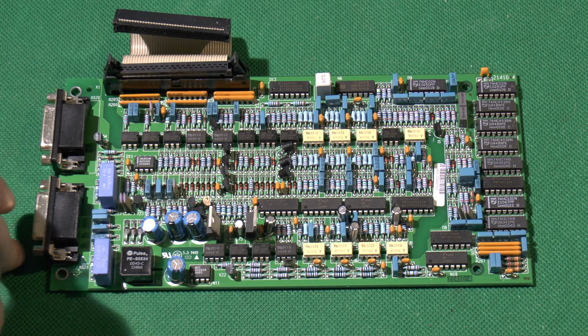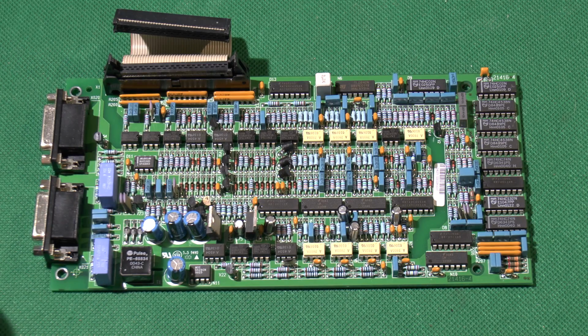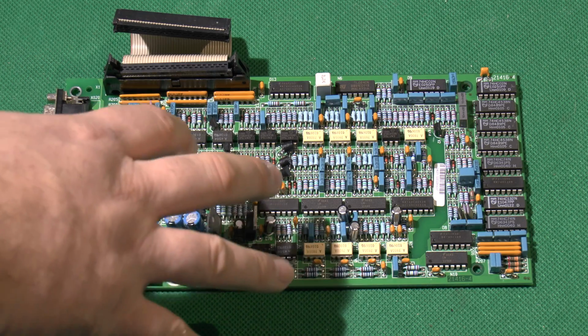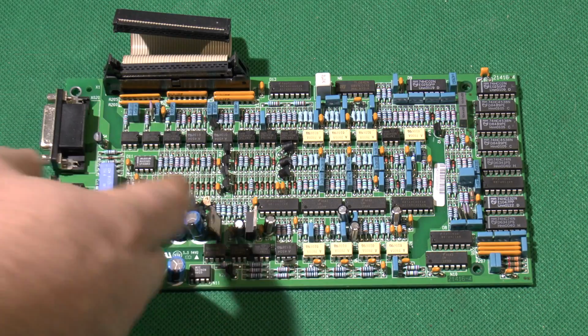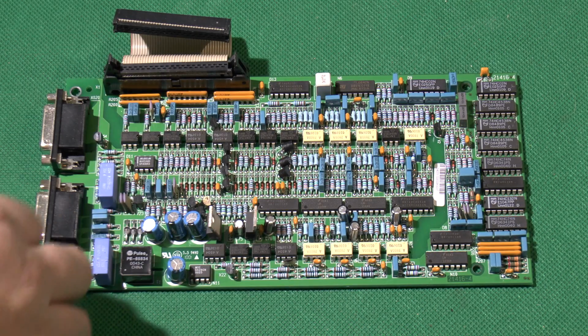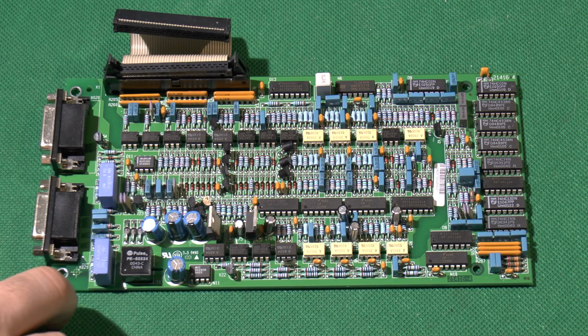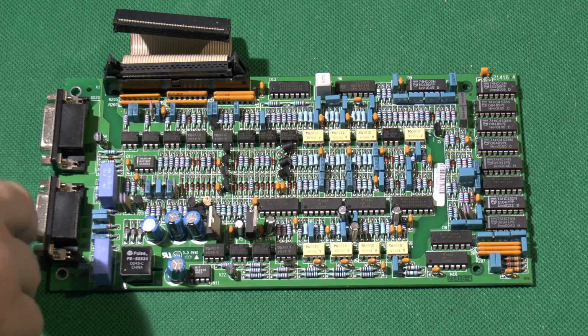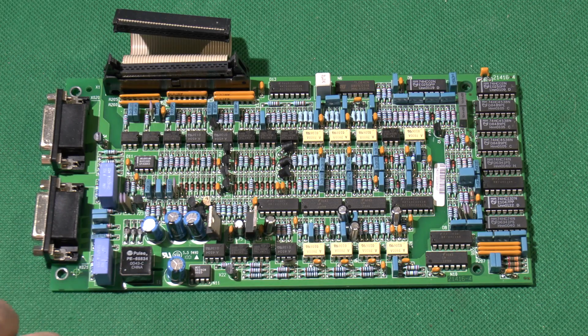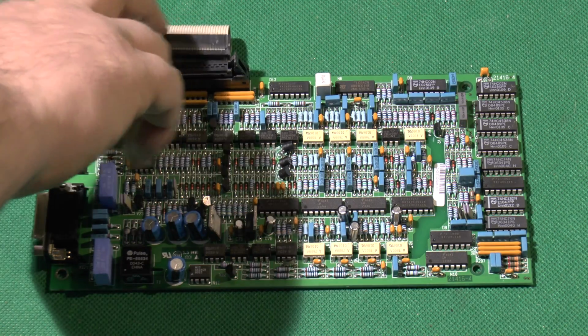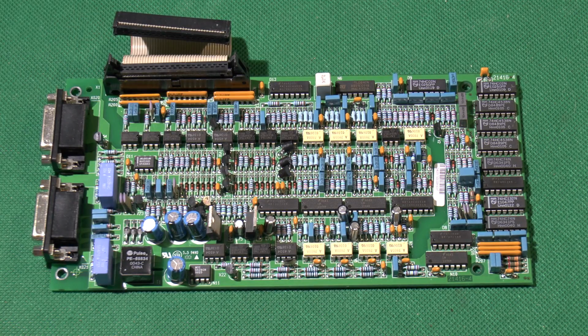For example, an N+1 redundancy setup where you've got, say, 5 UPSs, the load would be handled by any 4 of them, and you can take one down for maintenance without losing any resilience. In case of power failure, the rest can handle the load, then you can bring that one back in, take the next one in for service, and so on. If you're not running as a redundant set, this board is disconnected or maybe not even there at all.